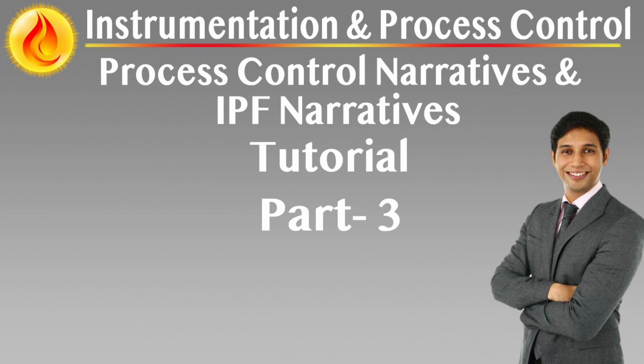Failure mode behavior. The narrative must define how the IPF is expected to behave in the event of key failure conditions such as sensor failure, e.g. open circuit, drift out of range, final element malfunction, e.g. valve fails to close, logic solver fault. For each failure mode, the desired system response is described, typically fail-safe behavior, fallback logic, or alarm and operator intervention.